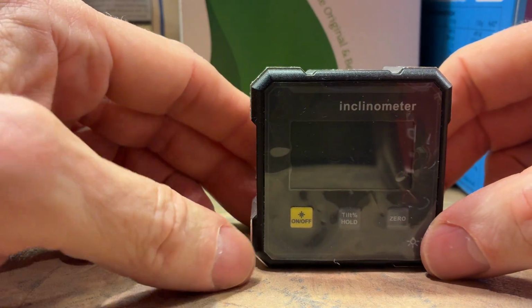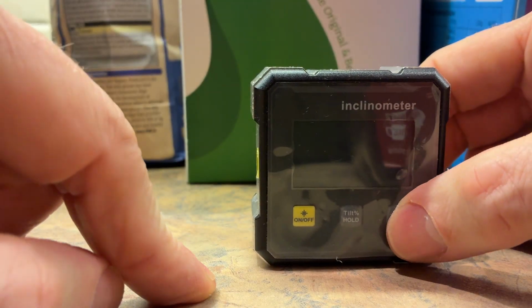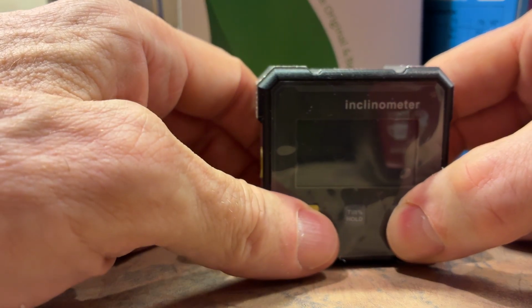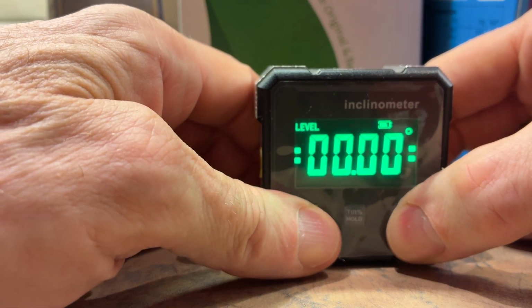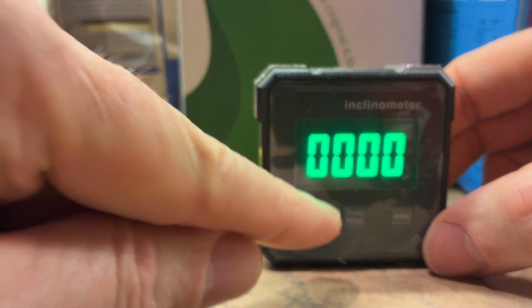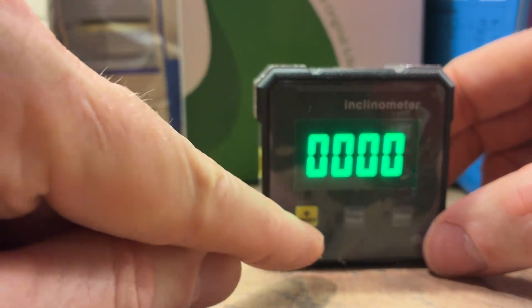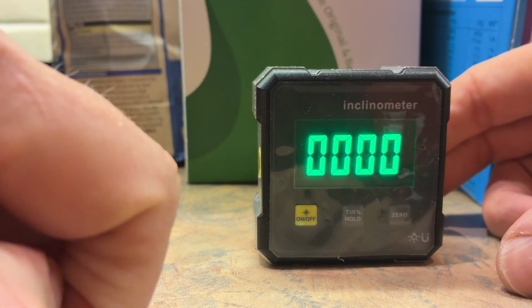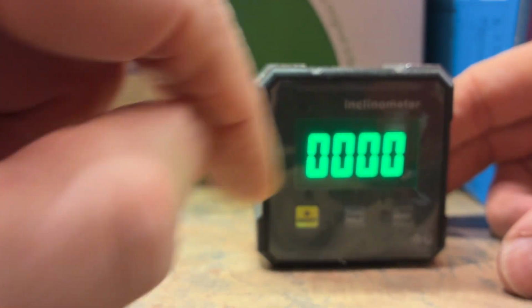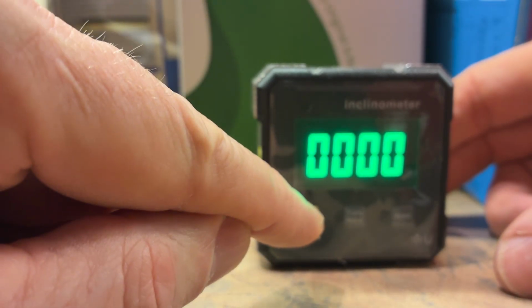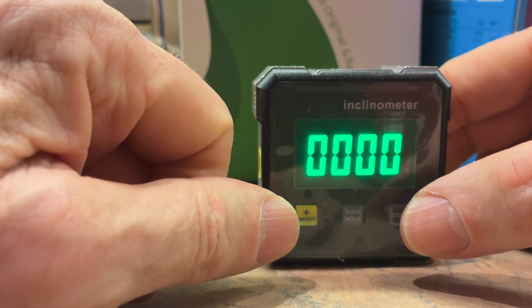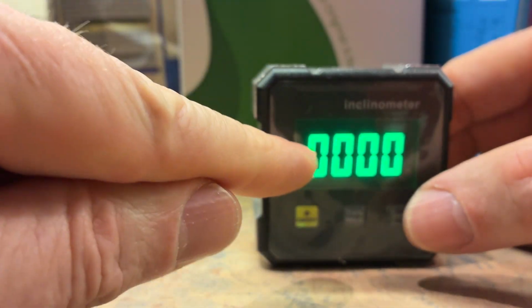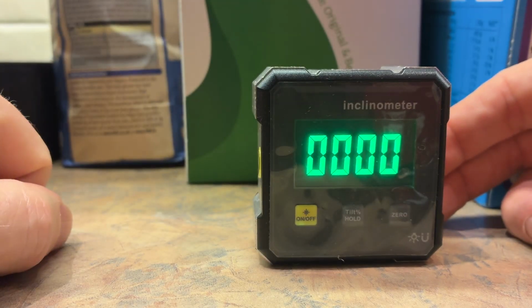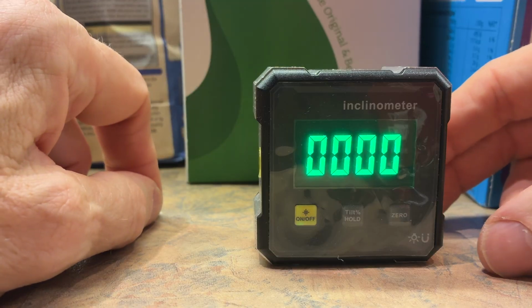So the way it works on this one is you press and hold the 0 button, and whilst you're holding it, you press and hold the on/off. It goes into its normal launch mode, but whilst you're holding both buttons, it then reverts and displays 4 zeros. The moment it displays 4 zeros, you release both buttons. If you get anything else on there, like little arrows, percentage sign, or hold, or level, you've not done it right. You've just got to turn it off and do it again. So basically, press and hold both buttons. As it boots, it reverts to 4 zeros, release both buttons. Once you've got the 4 zeros and nothing else, you are in calibration mode.